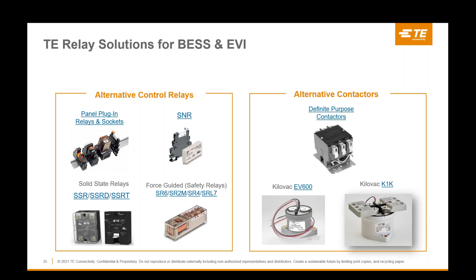And then in the contactor realm, we also have definite purpose contactors, which are AC contactors, as well as our Kilovac brand, under our different business units that Juan mentioned earlier in the presentation. We have the EV600 and K1K. These contactors can get up to the 600 to 1,000 amp range, and 1,500 volts.